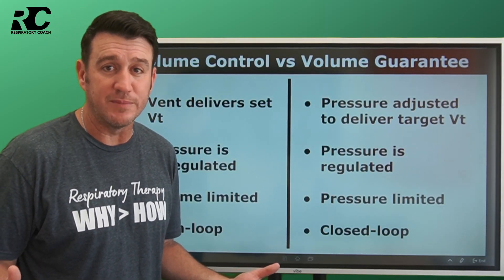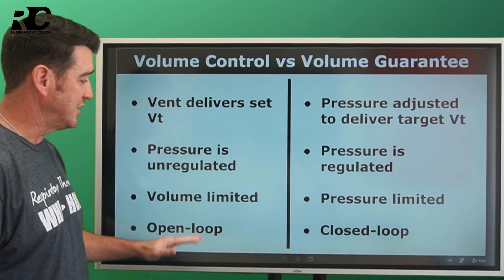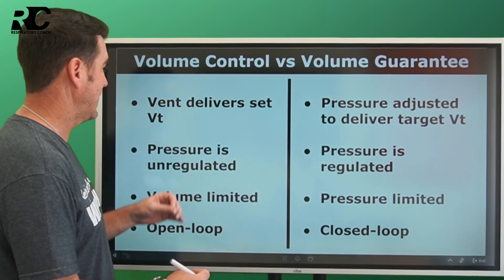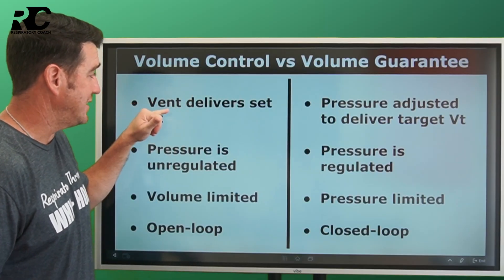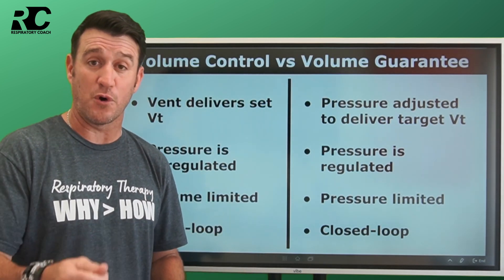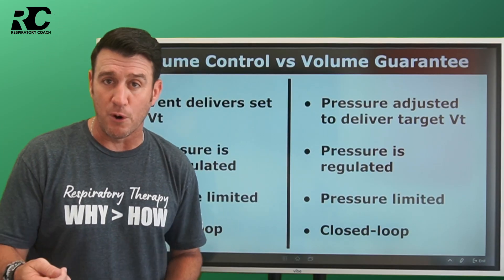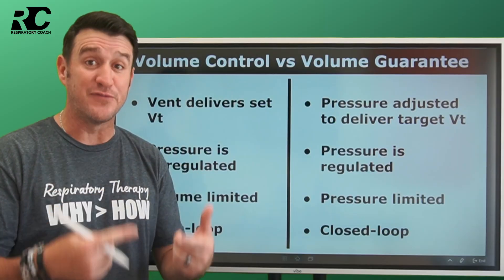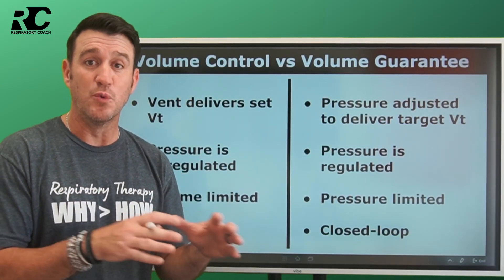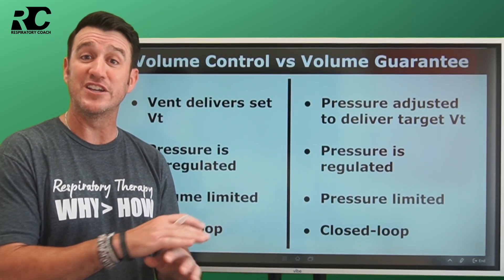Volume control versus volume guarantee — the screen is broken up into two sides. On the left side we see volume control features, and we're going to compare those to volume guarantee features. In volume control, the vent delivers the set tidal volume. You set a tidal volume — 450 milliliters, 400, 490, 500 — however many milliliters are appropriate for your patient — and the ventilator delivers that volume breath after breath. Any mandatory breaths will deliver that set tidal volume regardless of anything else.